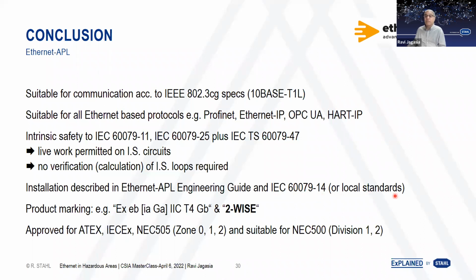And of course, you will have local standards, which local standards here would comply to NEC 500 or 505. Product markings will be similar here. As for IEC ATEX, it will be class 1, div 1, intrinsic safe, and then 2 wise. The labeling is still being evolved by the NFPA team, so I would wait for that labeling to come up. And definitely it is all approved and suitable for installations in div 1, div 2.